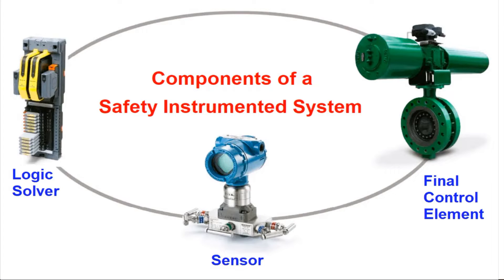The first component is the Sensor. This is used to measure process parameters such as pressure, temperature, flow, differential pressure, etc. It preferably has SIL — Safety Integrity Level — certification. It is preferred to have such certification for these sensors.